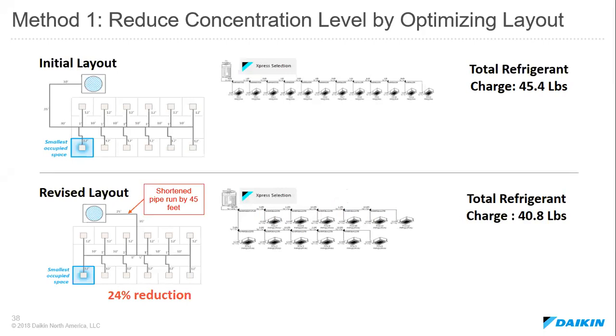Method one, reduce concentration level by optimizing our layout. In our initial layout at the top of the screen, you'll see we have an outdoor unit at the very top of the building. We've got a long run of pipe that's going to be 95 feet to our first branch, where our smallest occupied space is located. In this case, if we were to look at how much refrigerant is in the outdoor unit and all the affiliated piping in this system, we have a total charge of 45.4 pounds. That could be a problem for that space.